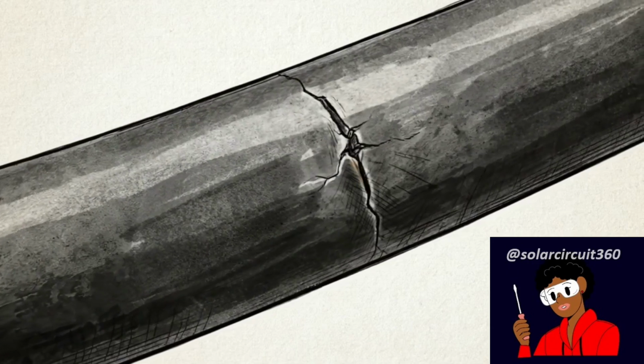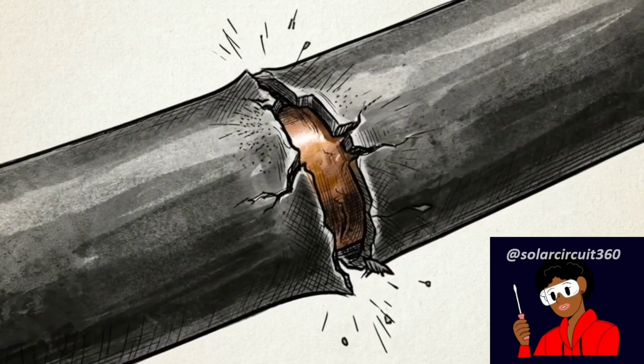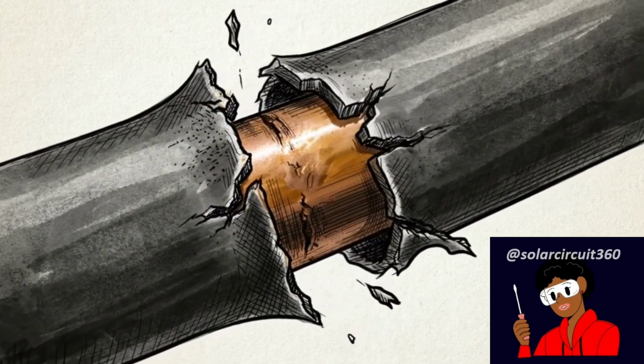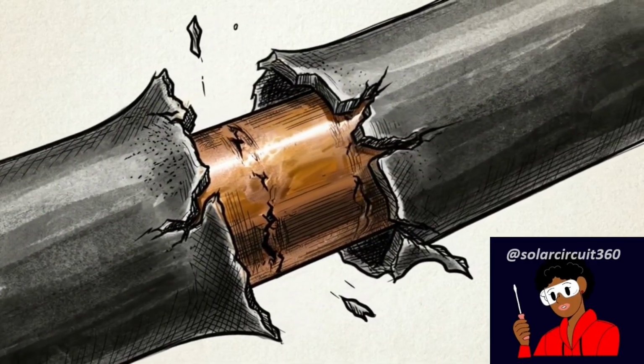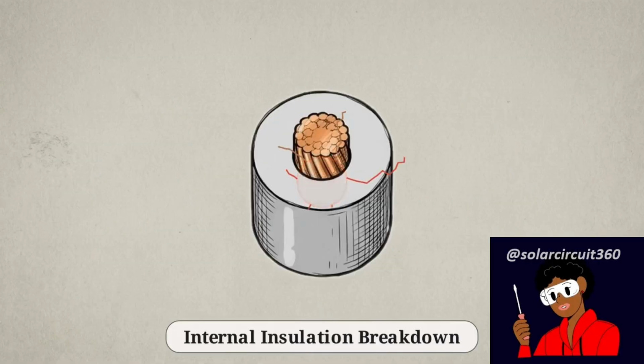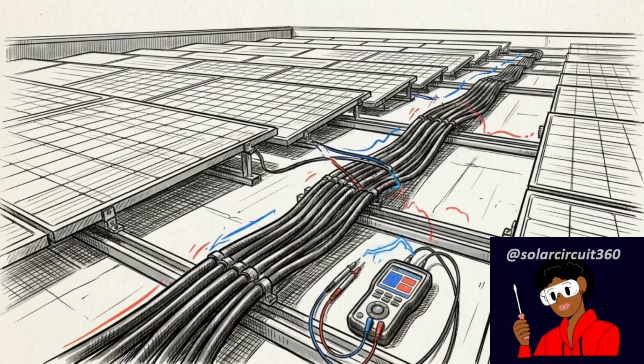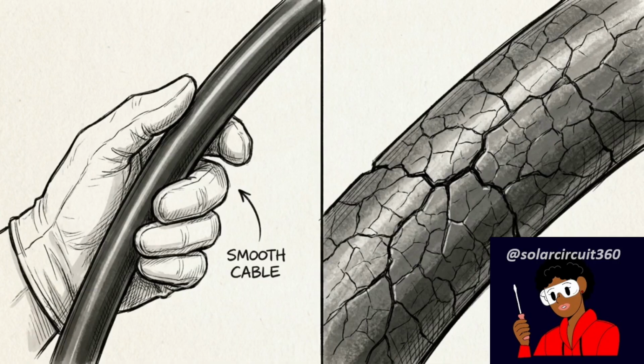While solar panels are built for decades of service, the transmission cables connecting them are subject to a specific set of failure modes, most notably internal insulation breakdown that moves from the conductor outward. On a rooftop, daily thermal expansion cycles combined with intense ultraviolet exposure gradually alter the molecular structure of the cable's protective jacket. This degradation is often invisible during a standard visual inspection, as the physical cracking can remain microscopic while still compromising the cable's dielectric strength.